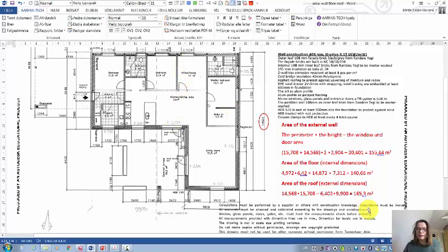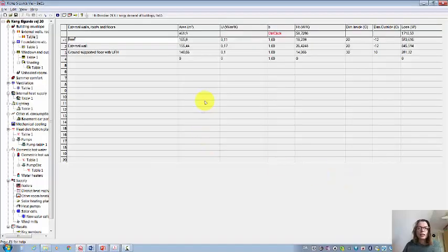So that's what we have here. And then we have the U value for the floor, and then we have the B factor. And for the B factor here, we have underfloor heating, right? So we have 20, and then we have 10. That means the B factor is going to be 1. Then this one is calculated by the program itself, and also the heat loss.